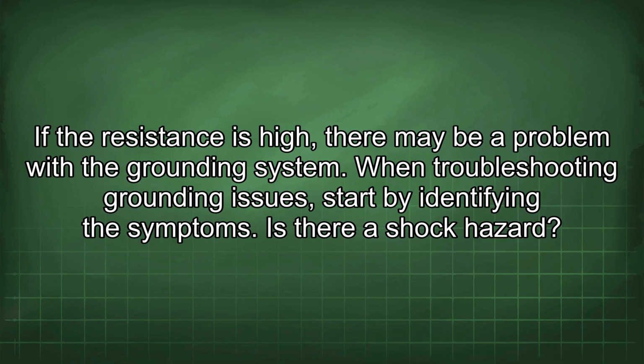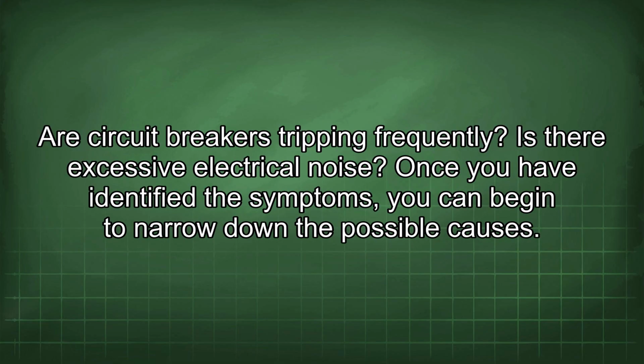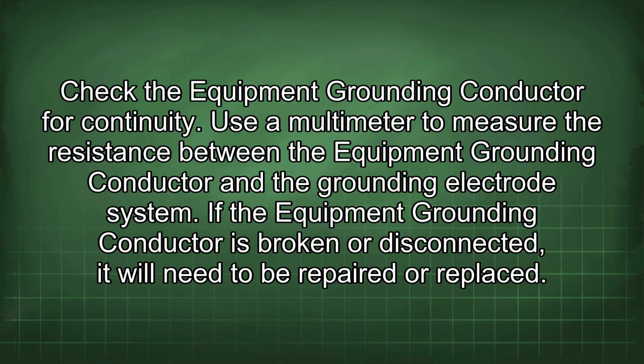When troubleshooting grounding issues, start by identifying the symptoms. Is there a shock hazard? Are circuit breakers tripping frequently? Is there excessive electrical noise? Once you have identified the symptoms, you can begin to narrow down the possible causes. Check the equipment grounding conductor for continuity. Use a multimeter to measure the resistance between the equipment grounding conductor and the grounding electrode system. If the equipment grounding conductor is broken or disconnected, it will need to be repaired or replaced.